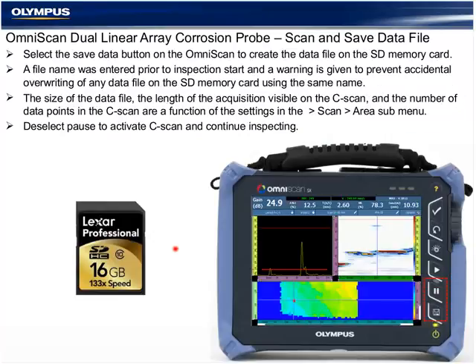So once the probe is coupled well and scanned over a component, the C-scan is built. Both the pause and save data buttons are available right from the instrument to save the C-scan to the SD memory card. The size of the data file, the length of the acquisition visible, and the number of data points in the C-scan are all a function of the things we just looked at under the scan menu. Selecting unpause, or deselecting pause, will activate the C-scan and continue inspecting.